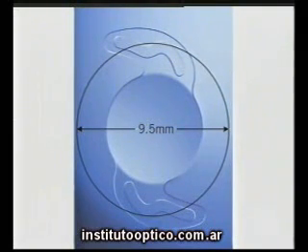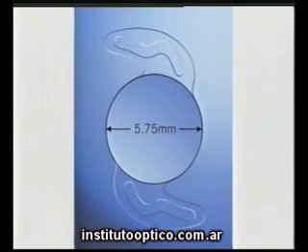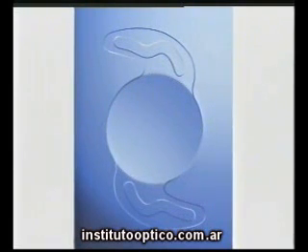The optic body diameter of 5.75mm has been chosen to facilitate the ease of implantation with the Rayner injector system, whilst maintaining optimal optical performance. The Rayner Centerflex lens also incorporates the latest thinking in square-edge optic design.